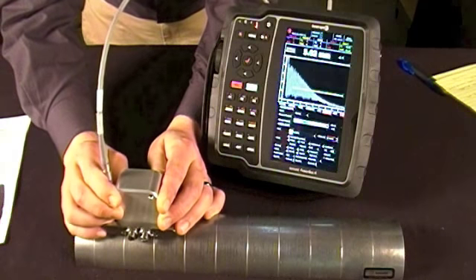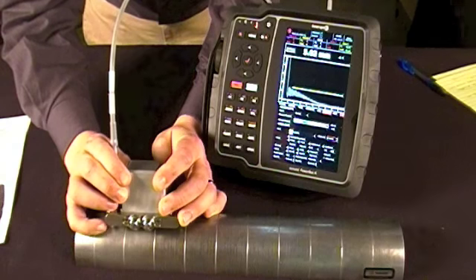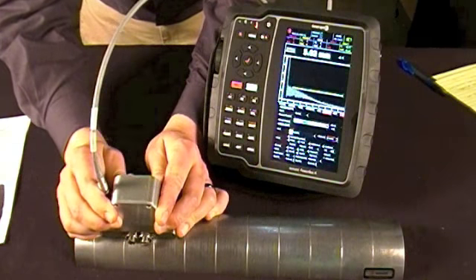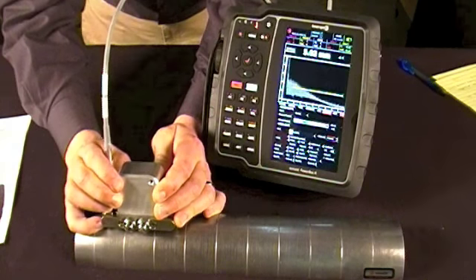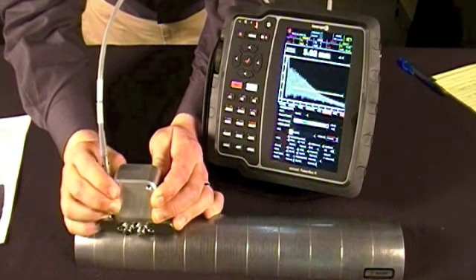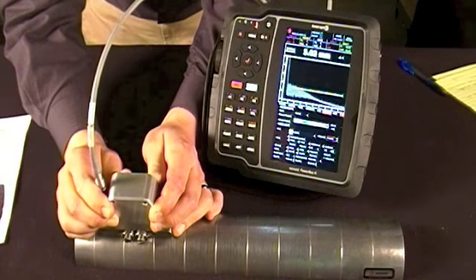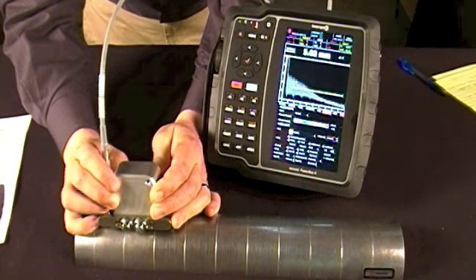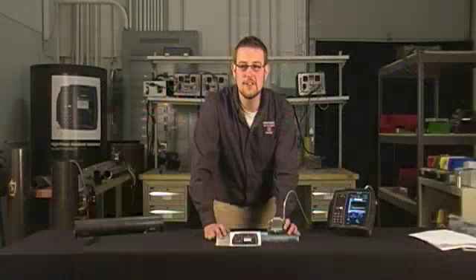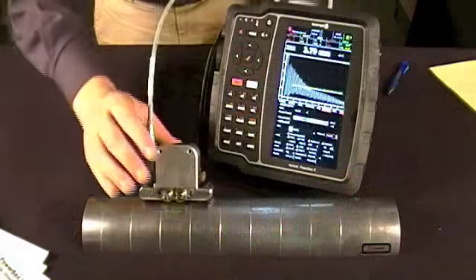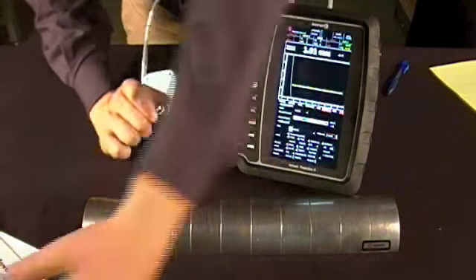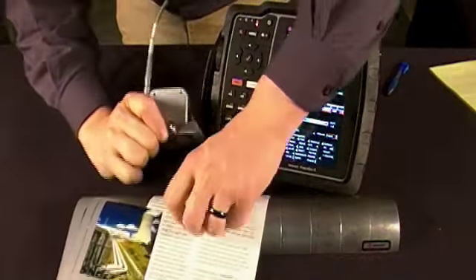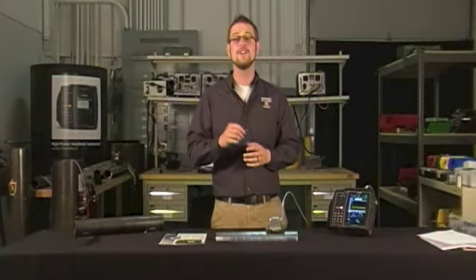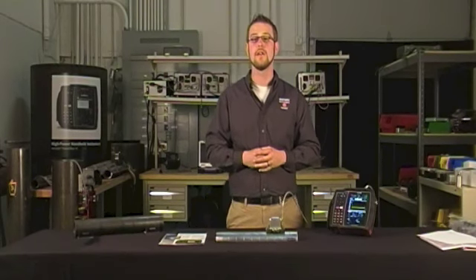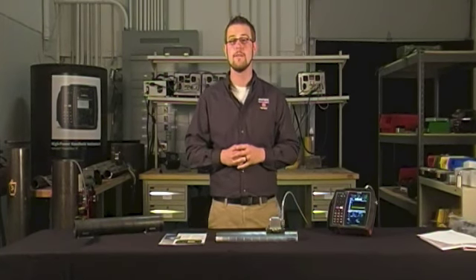Unlike other ultrasonic thickness measurement devices, EMAT sensors are tolerant to changes in sensor position while maintaining accuracy. That gives this device superior thickness measuring capabilities in less than ideal conditions. Additionally, EMAT allows for sensor liftoff of up to 12 millimeters, allowing for penetration through paint, rust, and other surface conditions. Well, that's it. You've just finished the thickness measurement tutorial, and hopefully results came out as clear as mine.